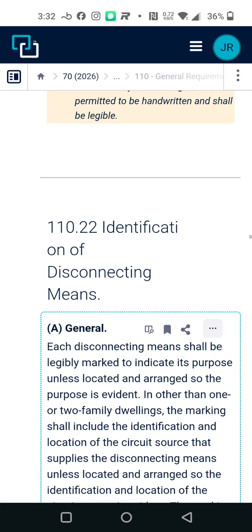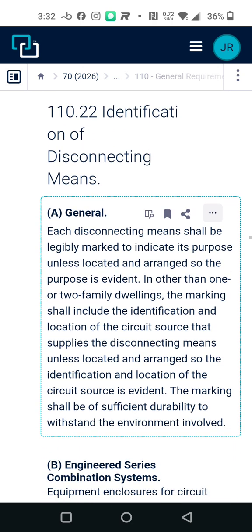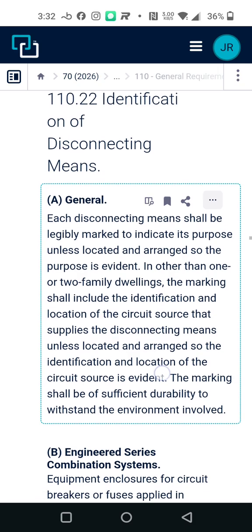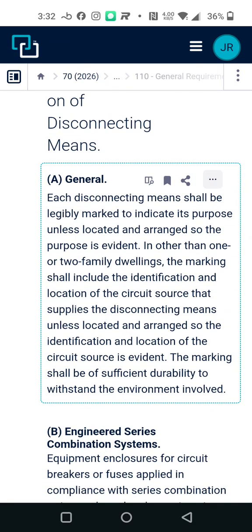Identification of disconnecting means. Each disconnecting means should be legibly marked to indicate its purpose unless located and arranged so the purpose is evident. And other than one or two family dwellings, the marker shall include the identification and location of the circuit source that supplies the disconnecting means unless located and arranged so the identification and location of the circuit source is evident. The marker should be of sufficient durability to withstand the environment involved.